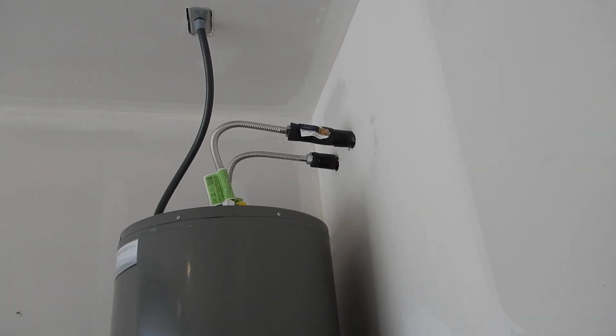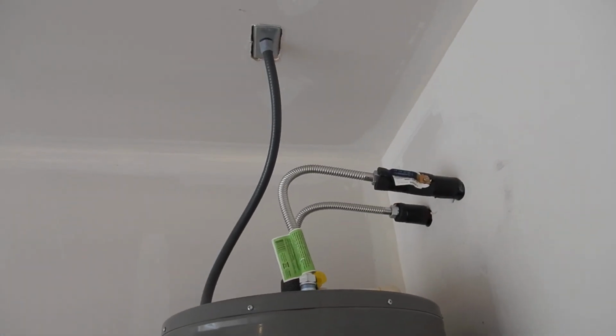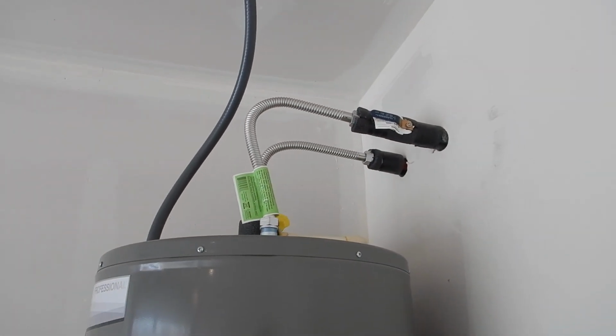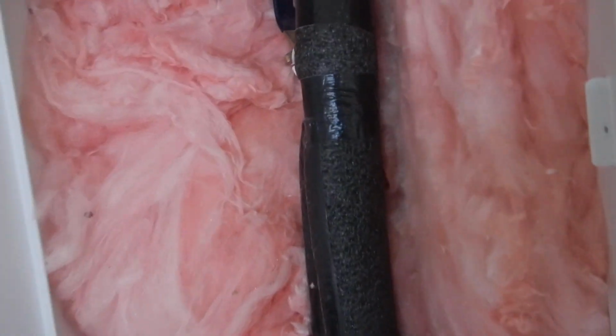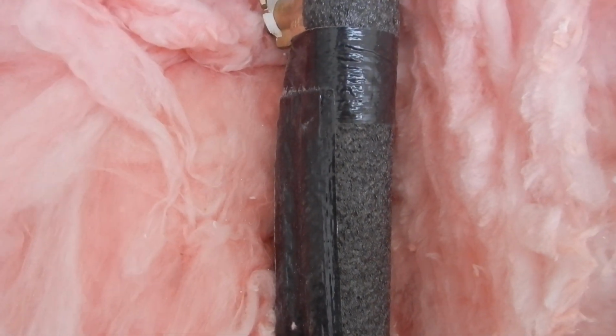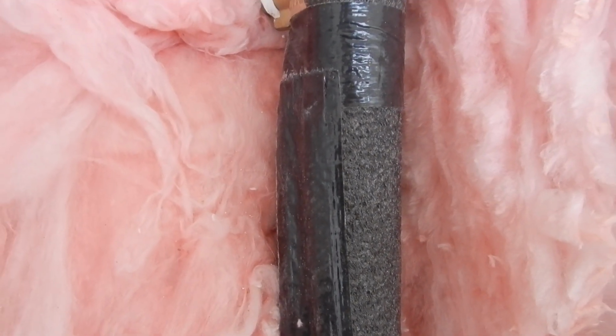So you have over 80 psi, you need an expansion tank. You need a check valve and a regulator valve, that's the word I was looking for. We do not have a regulator valve, we do not have a check valve, and we have over 80 psi.